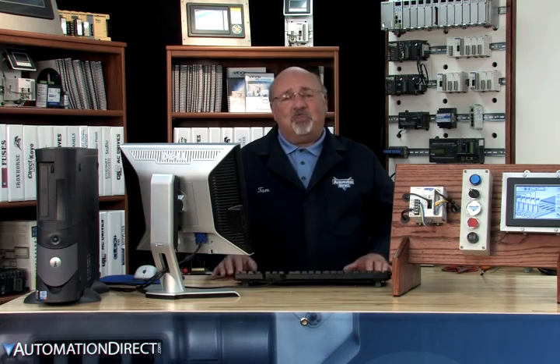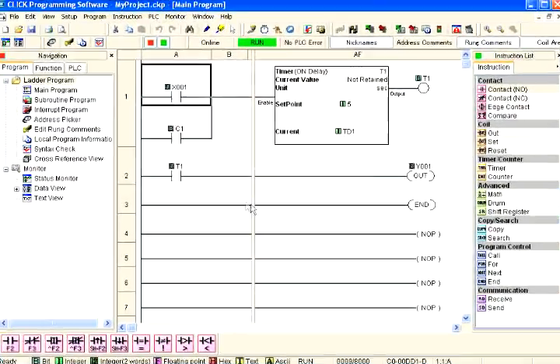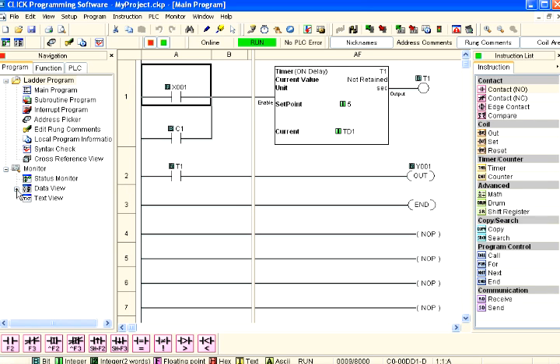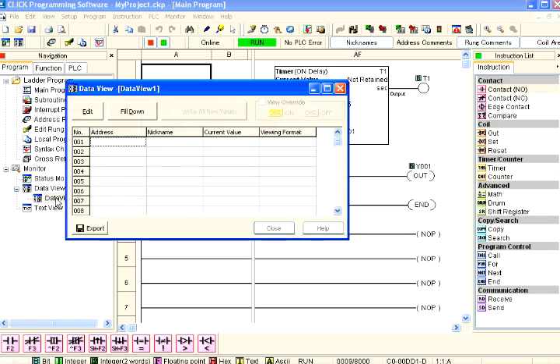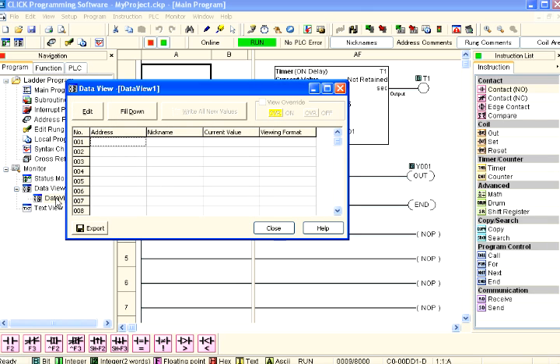Data View is the built-in software feature we can use to test our ladder logic program. The Data View dialog box can be accessed as shown here. From the navigation window on the left side of the software development screen, select the program tab, open the Data View folder under Monitor, and double click on Data View 1.